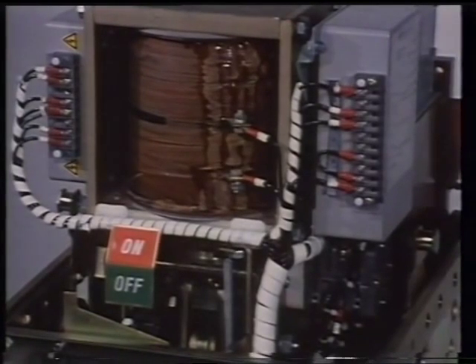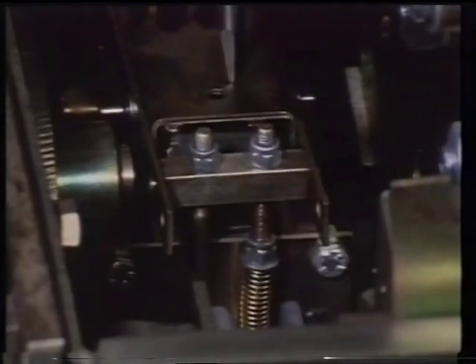We now move on to the AC generator's circuit breaker. We describe its function and show what to do if it fails to close normally. An AC generator circuit breaker is designed to connect the AC generator safely to the bus bars, as well as disconnect it automatically if serious malfunction occurs in the system. Here is a solenoid-operated air breaker with undervoltage relay and trip.